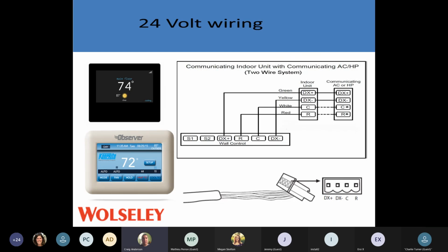If you're working on communicating systems, it's a little bit different. We're checking R N C. R N C is our voltage that is going to our outdoor unit or to our thermostat. Typical communicating wiring is 4 wires outside, depending on the unit. Some of them are only 2 wires. Look at the schematics on that unit. And then 4 wires to our indoor unit via a green plug to connect the units to the board downstairs.